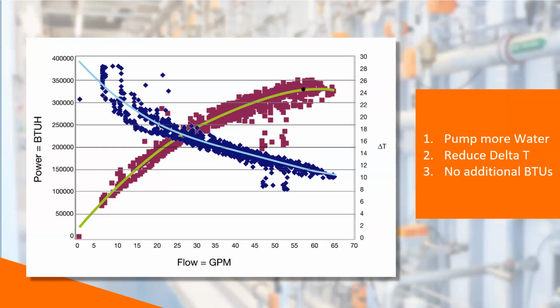But if we look at this dot on this slide, that represents approximately 320,000 BTUs. If we draw a line straight across, you can see how that same load can be achieved at multiple flow rates by leveraging that thickness of the coil curve. Will we be able to do this at all times? No, but as this point cloud indicates, there are many times where we can have lower flows and still achieve that same BTU output. So if you look at this, because we talk about partial loads, we still have a thickness. It's likely due to normal variations in the heat transfer, but we can still achieve the same BTU output with multiple flows.